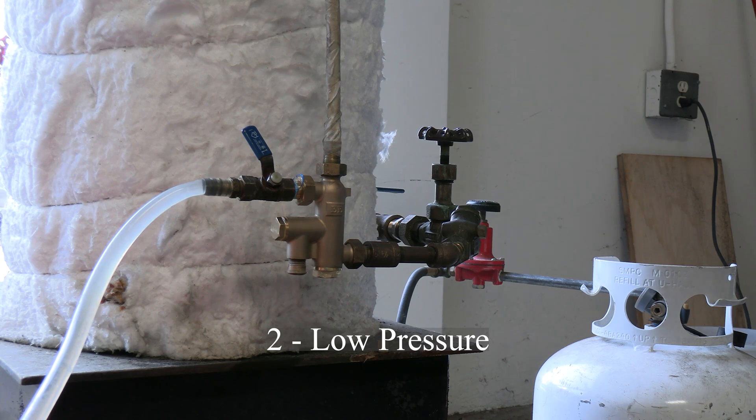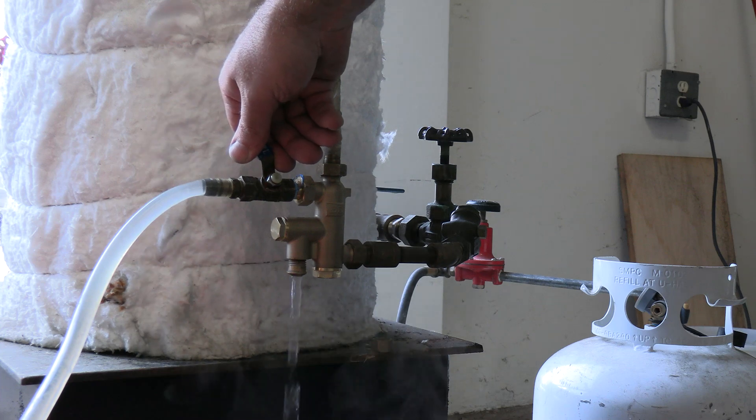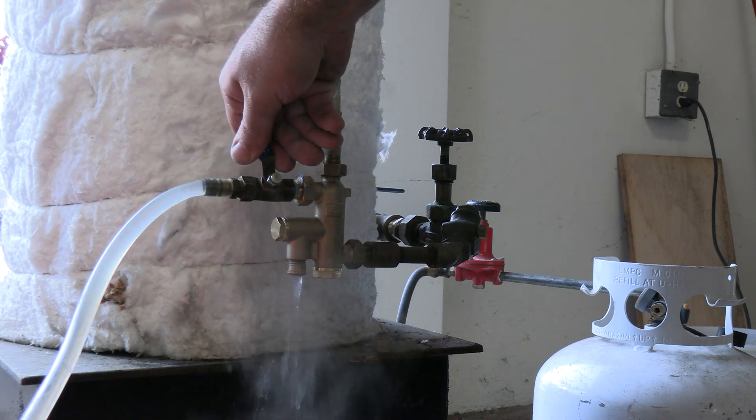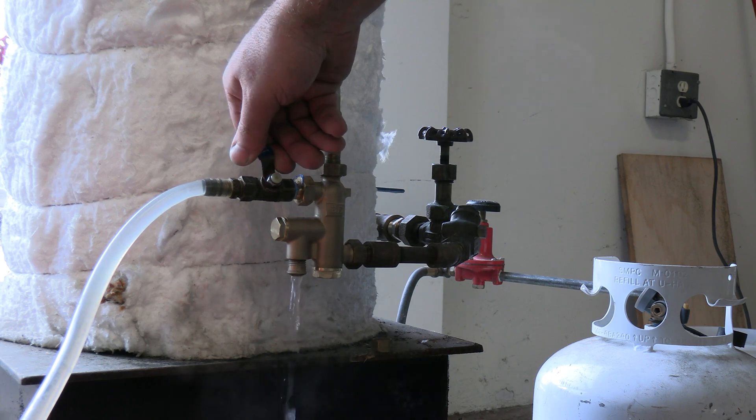Now we'll take a look at how the injector behaves when it's at the absolute bottom limit of its operating pressure. Everything appears to be normal, but as the water is cut back, it turns fairly quickly from a solid stream to a mix of water and steam.